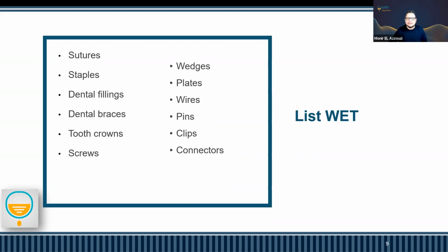These are considered technologies that are well known on the market. So they don't have to go through a full review by an expert panel or a full review by a notified body. They will be considered well-established technologies, and then there is no need for a clinical investigation, no need to make what we call an implant card, etc. So there are a lot of things that you can avoid because these products are considered well-established technologies.